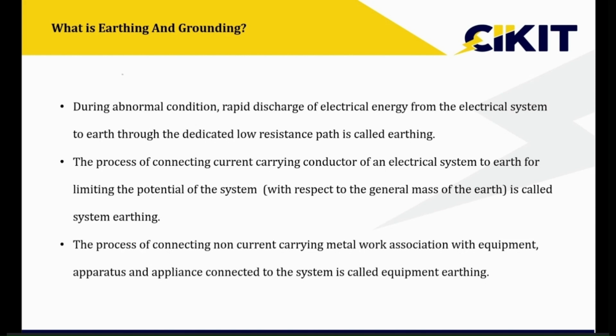Depending upon the connections, the earthing can be classified into two types. If I'm connecting the body of an equipment to the earthing, it is called equipment earthing or body earthing. If I'm connecting the neutral of the system to the grounding, it is called system earthing.